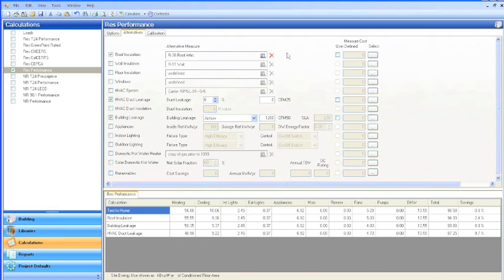So just to let you know what's going on here, I turned off the measured duct surface area menu. That seems to have fixed the problem. So just remember, if you have to use it, make sure you put in the proper lengths. I think one of my lengths was 0, and that was an unusual entry, and I think it messed up the numbers here. So when I turn that off, it's now calculating as expected. And these boxes went back to 0, and I know that it doesn't affect anything anyway, according to Energy Soft. So as you saw, just a little bit of troubleshooting got me out of that problem.